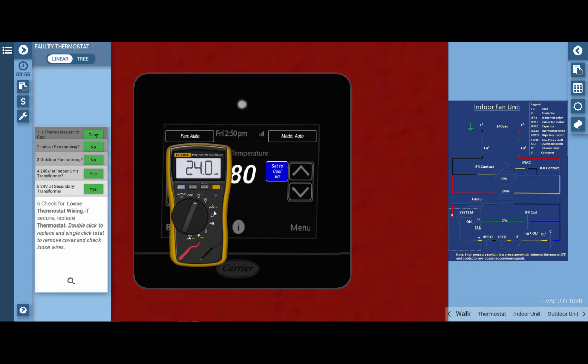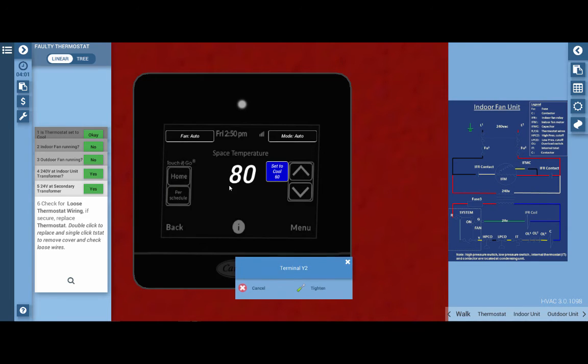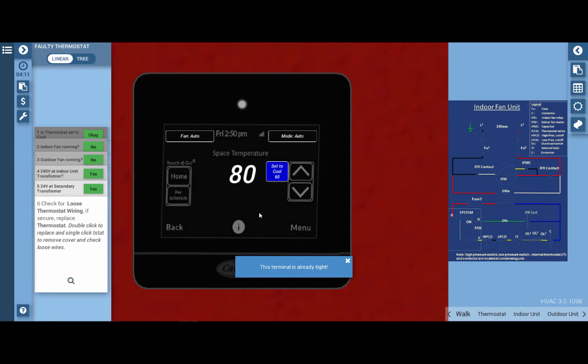We want to just kind of store the meter leads away for now in the meter right back in the toolbox. We want to open this thing up and just tighten the terminals, which we've done. It already states the terminals are already tight. So our next step is to simply replace the thermostat.